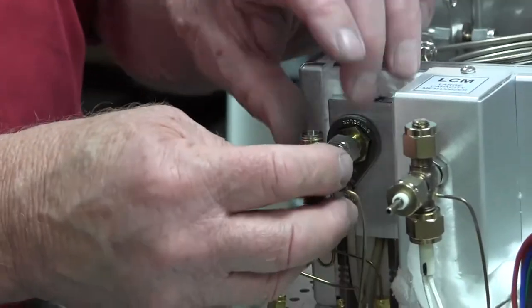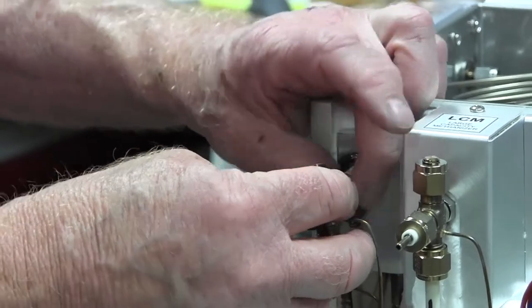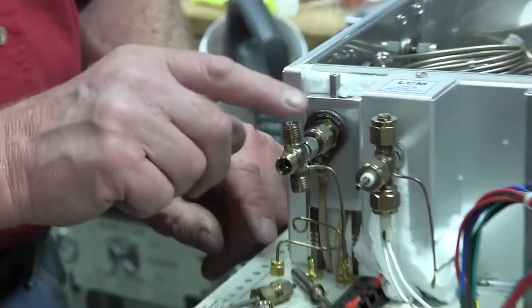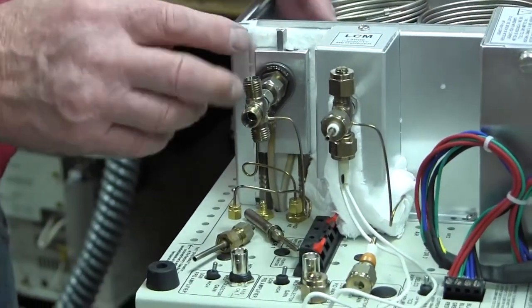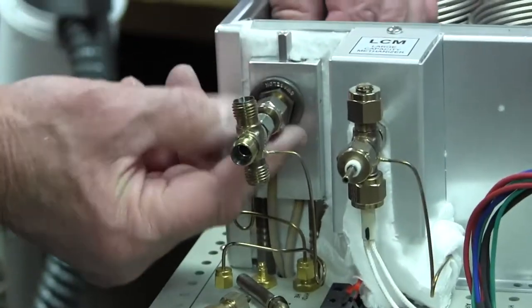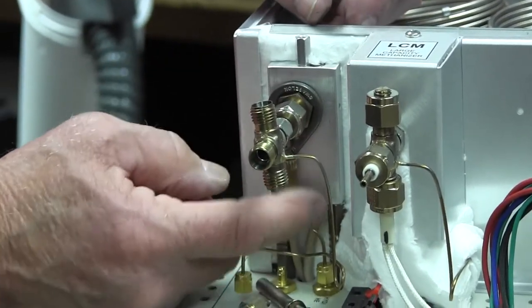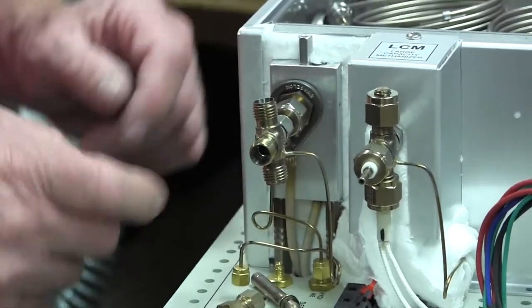When the methanizer is working perfectly, at 300 degrees is what we normally set the temperature of the methanizer tube. It's this aluminum block here that really heats that tube, so it's really the temperature of this aluminum block that you're setting.